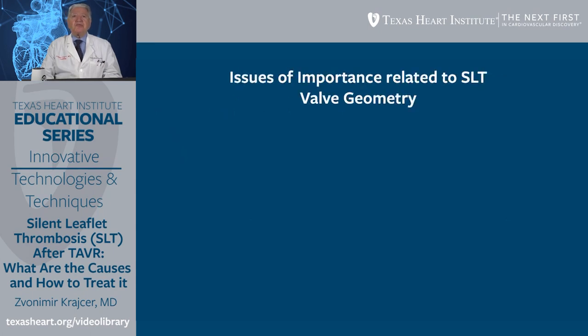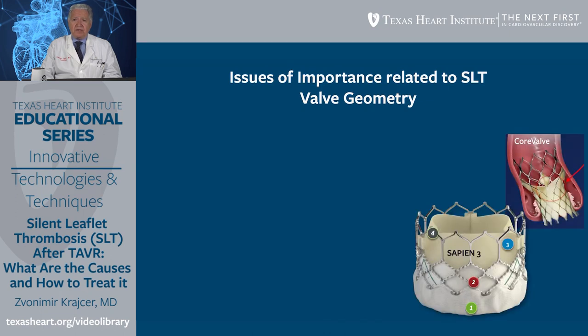Regarding valve design and geometry, three TAVR prostheses are currently approved in the United States. The two most commonly used are Sapien 3, a balloon-expandable valve, and CoreValve, a self-expandable valve. Sapien 3 consists of a metallic stainless steel frame, bovine pericardium leaflets, polyester material on the outside for prevention of aortic perivalvular leak, and suture material integrating all three components.